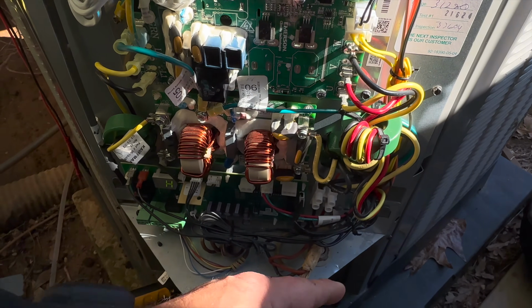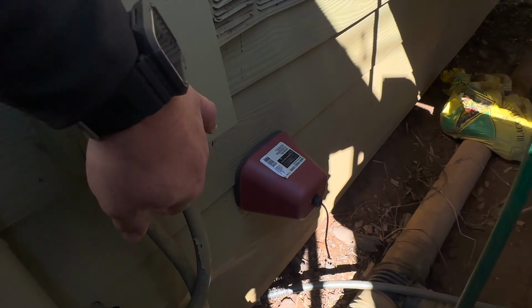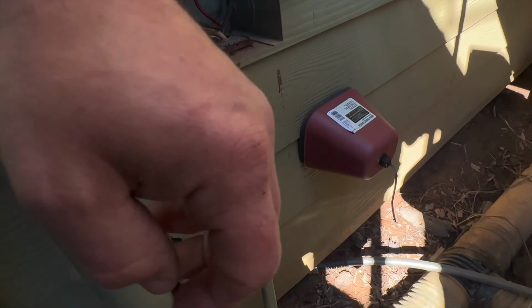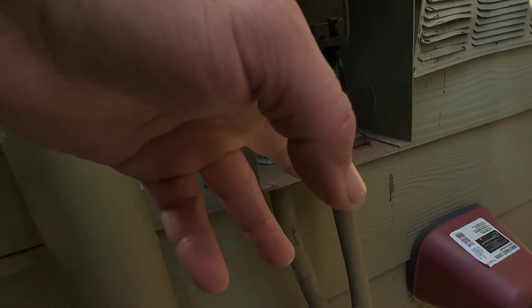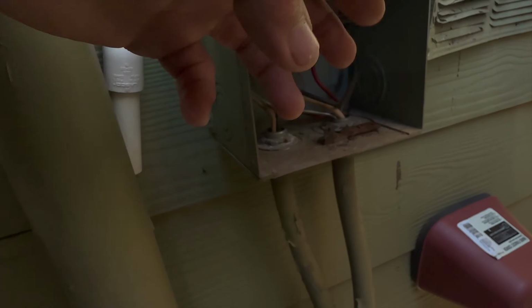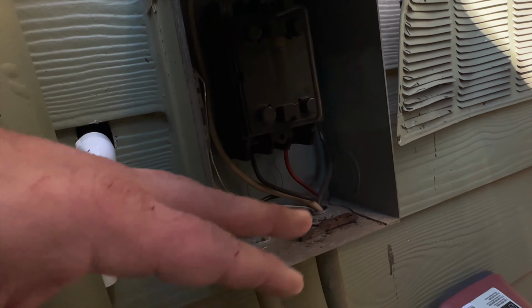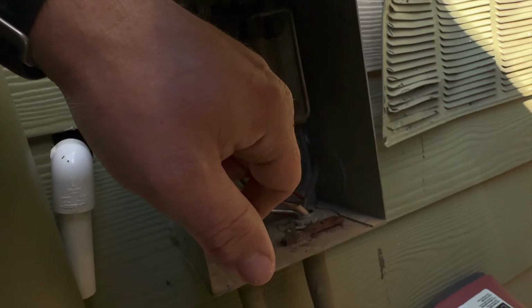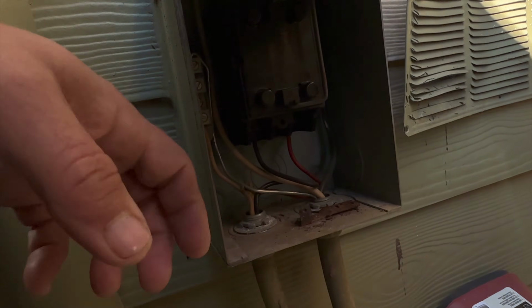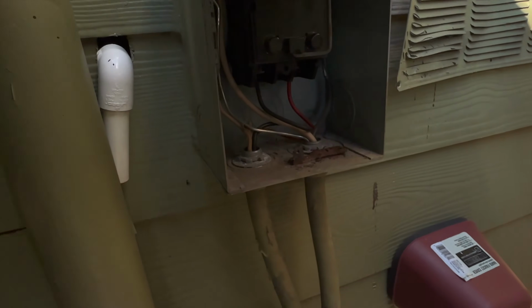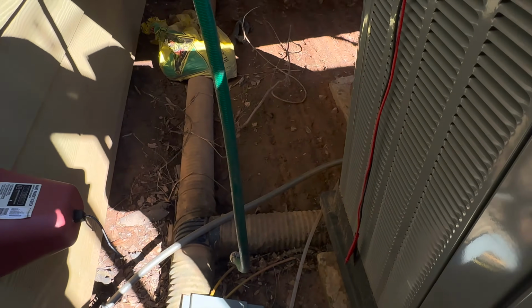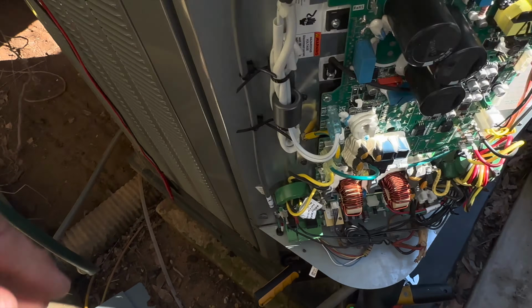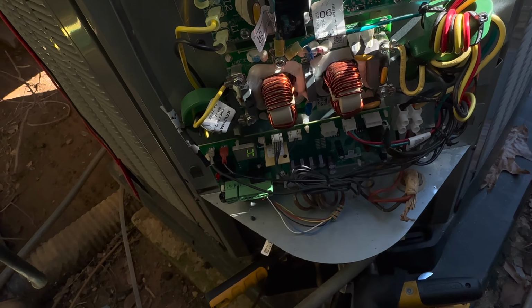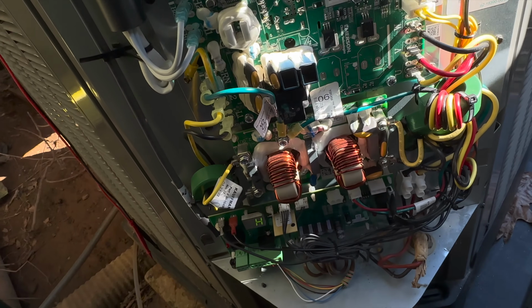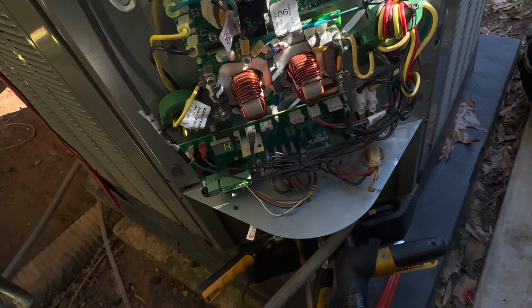First thing I did was check the power coming to the board, and there wasn't any. And this disconnect, I checked it, had power off the top but not coming out. Wiggled it a little bit and it came on and it restored power. So there's a bad connection in this. So we need to replace this disconnect here. So now I just started it up to make sure everything's going to run good. Look how the pressures look, and hopefully it's just going to be switching this disconnect out and we can move on to the next one.